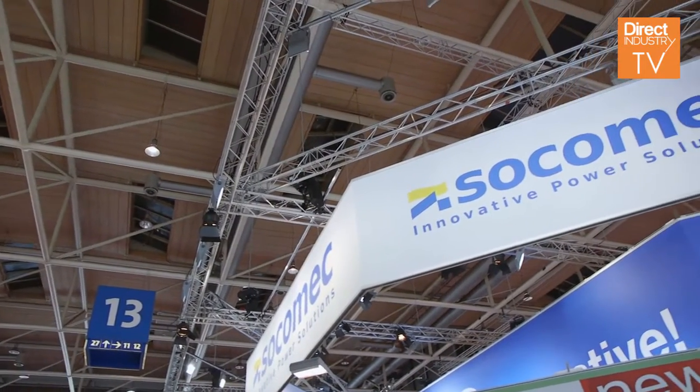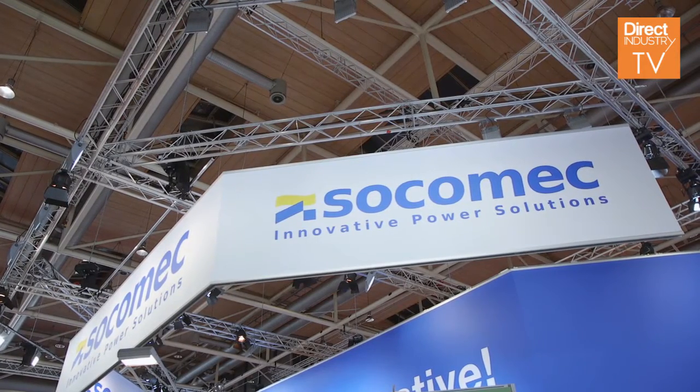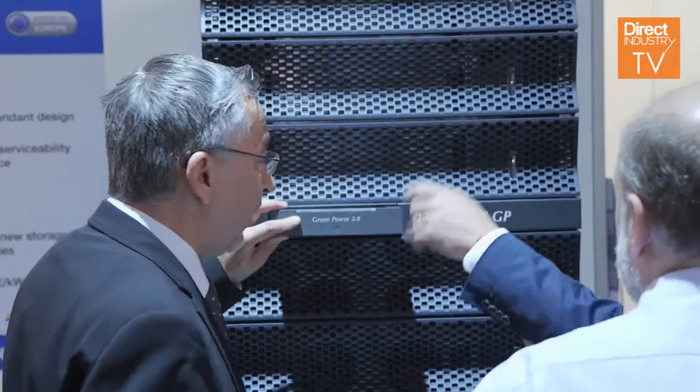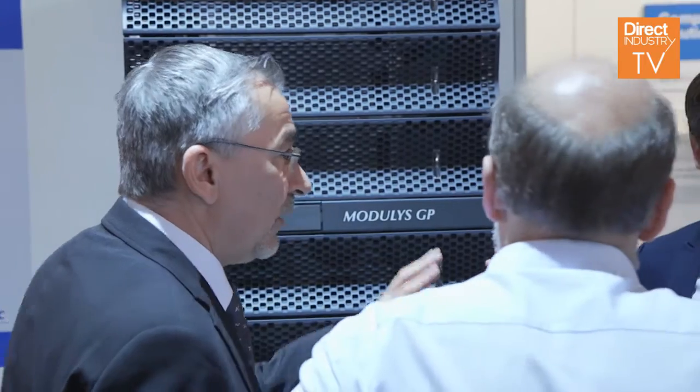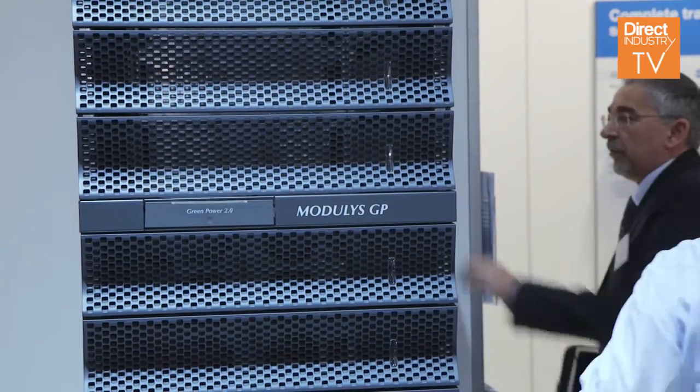Today we are going to speak about a new product that we have just launched, that is the Modulys GP UPS. Modulys GP 2.0 is a product that is based on a modular concept. It is composed of power modules of 25 kilowatts and in each cabinet, like the one that is behind my back, we can reach up to 200 kilowatts using eight modules.